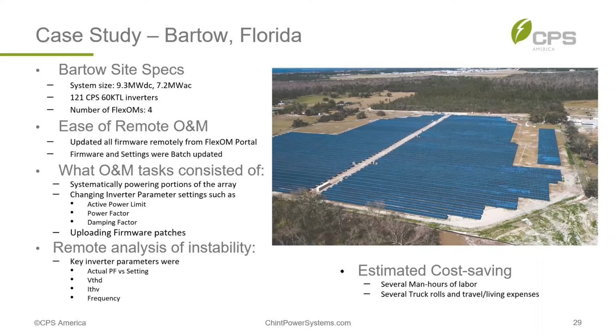Occasionally we were uploading firmware patches as needed. And the remote monitoring, by the way, the FlexOM portal consisted of analyzing the performance data and associating it in time with customer complaints to determine how to predict the onset of the instability and facilitate troubleshooting without negative customer impact. The important parameters were basically actual power factor versus the setting, voltage THD, current THD, and frequency.